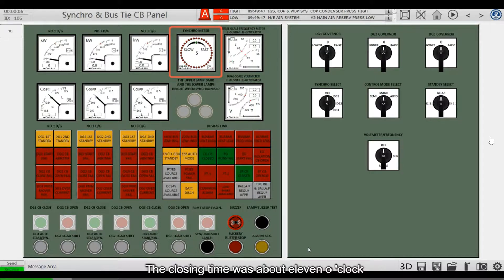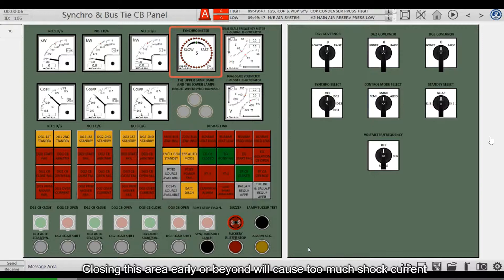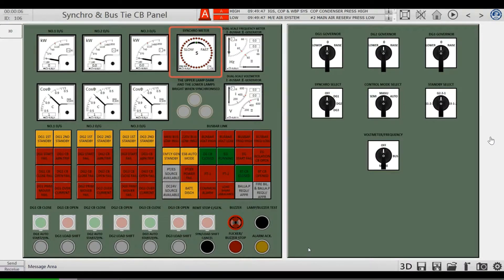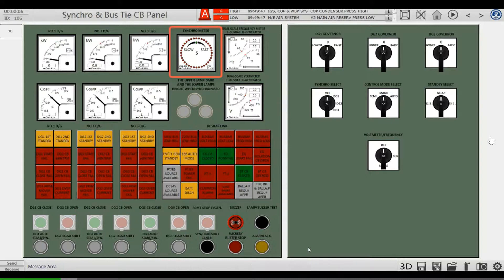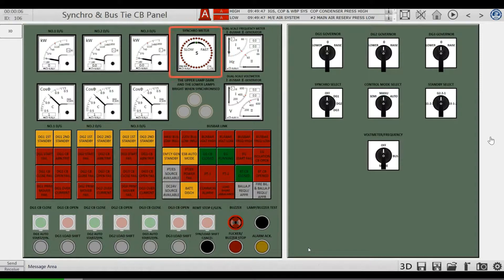The closing time is about 11 o'clock, and it is safe to close in this area. Closing too early or beyond this area will cause too much shock current and may cause closing failure. In severe cases, the generator running on the network will be removed, causing the whole ship to lose power.